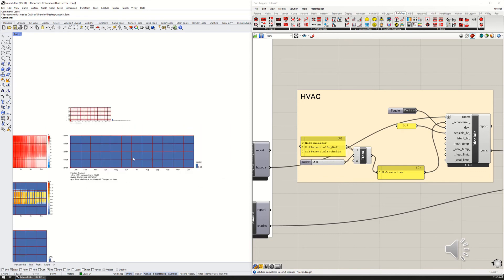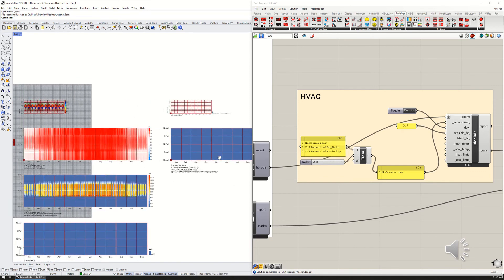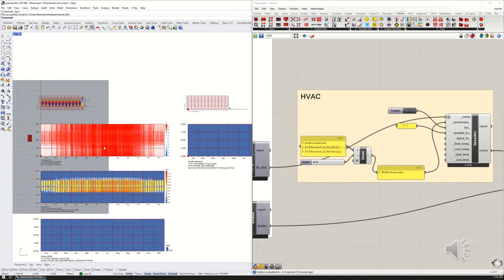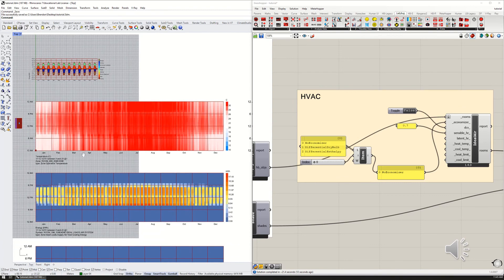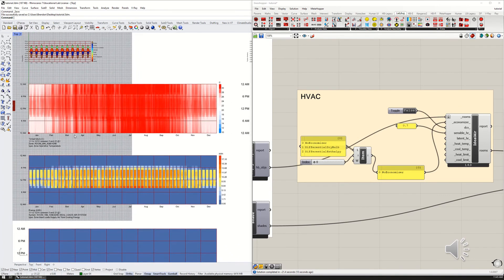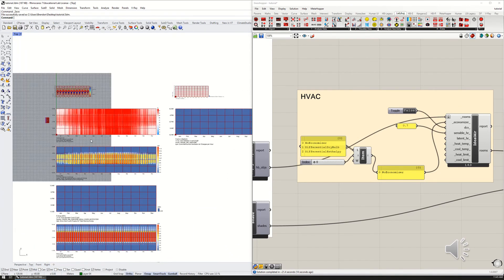There it is. So turning off the economizer there means that we got no airflow through the zone at all, and it further increases the temperature inside the zone and increases the cooling energy as well.